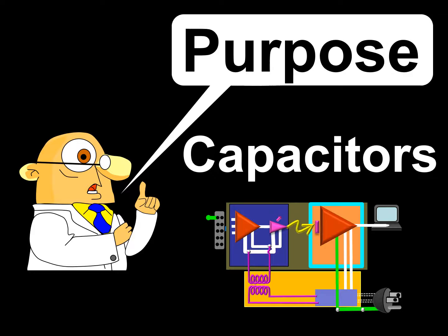Capacitors in the electronic circuit of the EEG machine are used coupled with diodes to act as power supply filtering devices and in isolation as temporary power sources. The purpose of a power supply filtering device is to transform alternating current into direct current. The purpose of a temporary power source is to supply electricity in the event of a power failure.